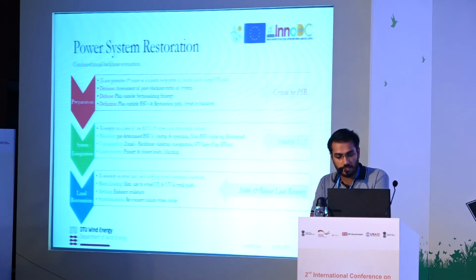The first stage is essentially the operator assessing the status of the system and then doing critical planning of the restoration paths and what Blackstart units to use to essentially avoid another occurrence of a blackout. Then Blackstart units, which are predetermined, are cranked up to power the non-Blackstart units, and regional network islands are formed because priority loads are picked up, but only to stabilize frequency oscillations, and the high voltage transmission lines are charged for propagating the voltage and getting the transmission system ready.